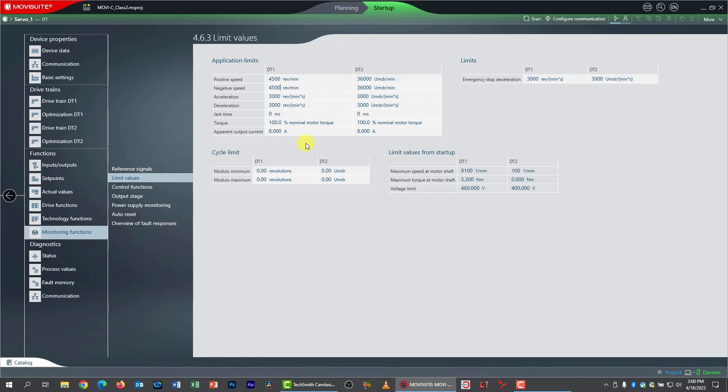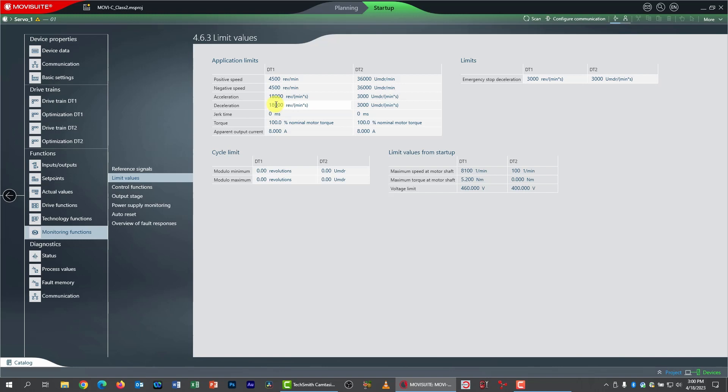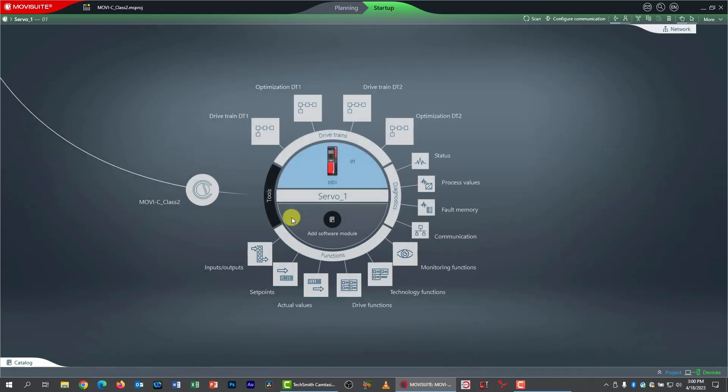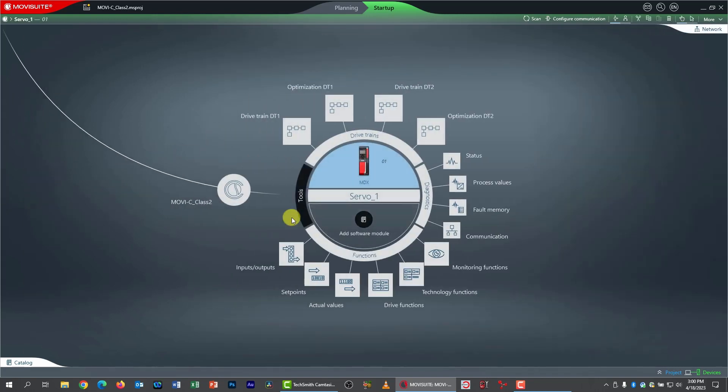it needs to be essentially four times the motor's nominal speed. That's 18,000 RPM per second. I know that seems incredibly fast, but actually it isn't. So there we go. We have now set our limits. And that is pretty much all we have to do. So we can go back to our access circle now.